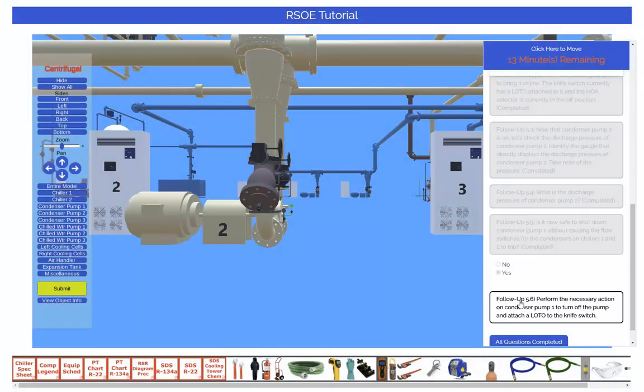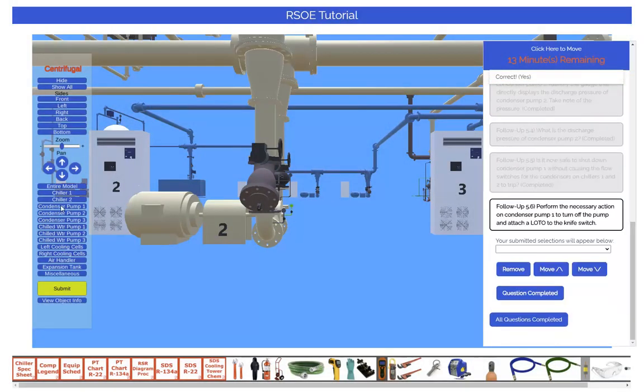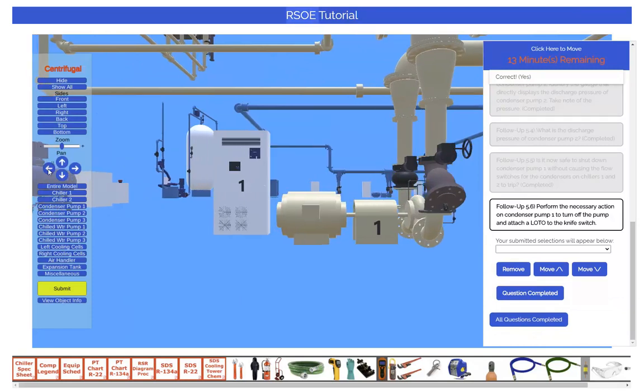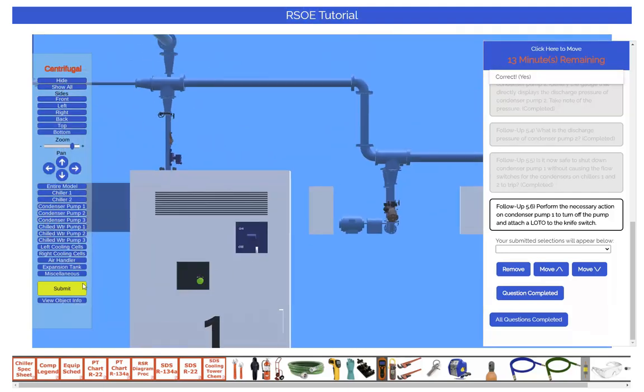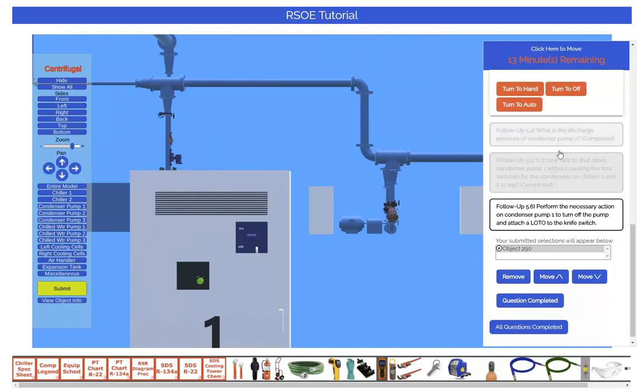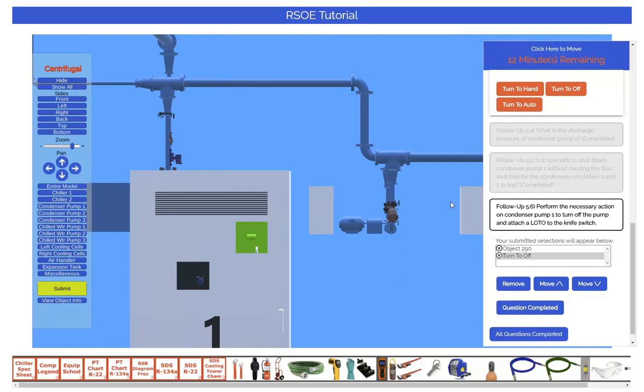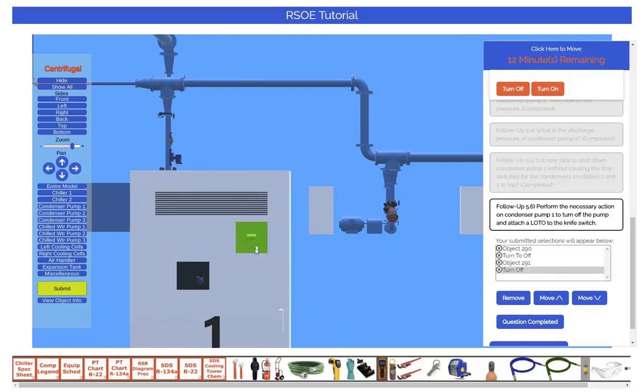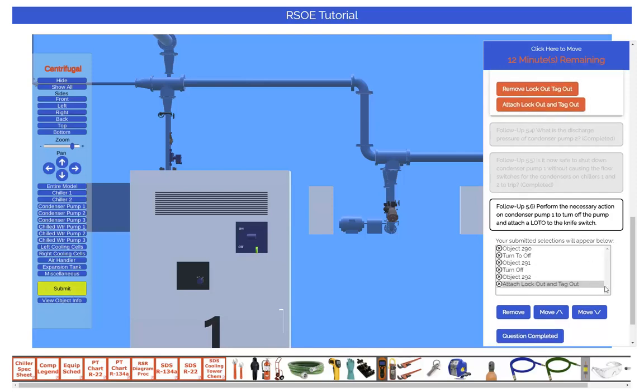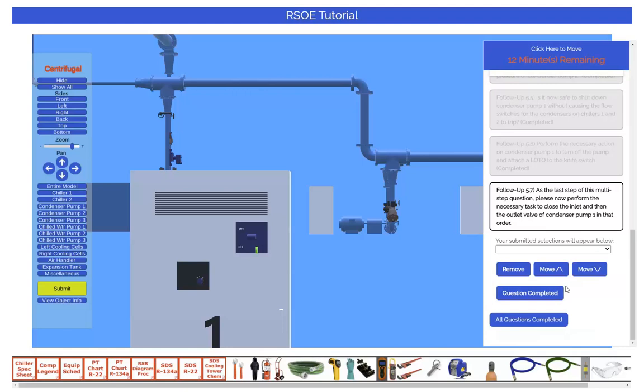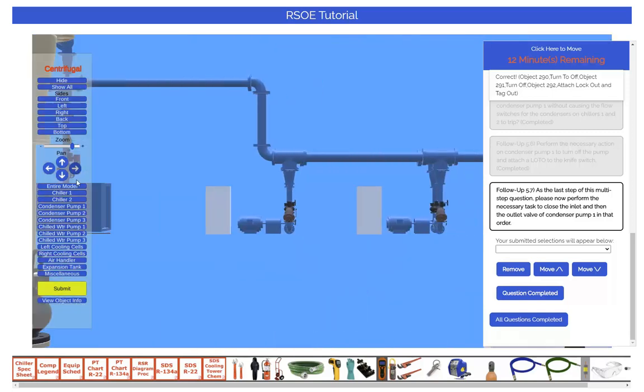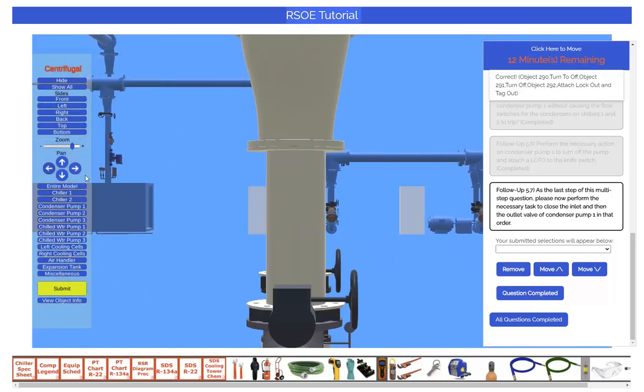This question requests that we turn off Condenser Water Pump 1. This involves turning the hand off auto switch to off. Next we should turn off the knife switch. And finally we will attach a lockout tagout to the knife switch. The last follow-up question requests that we isolate Condenser Pump 1 from the system by closing the inlet and outlet valves. Remember to pay attention to the order that the question asks — submitting answers in the wrong order will cause you to fail a question.